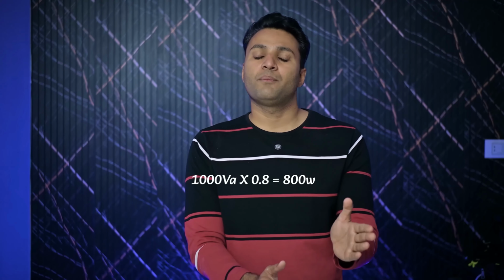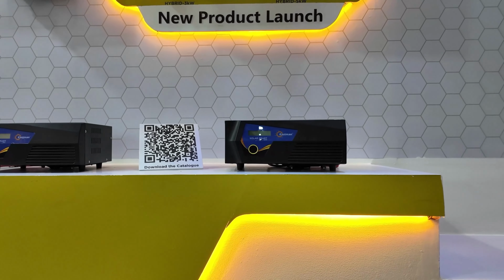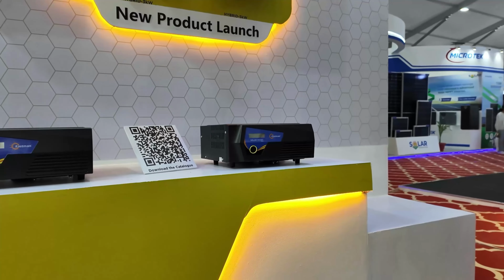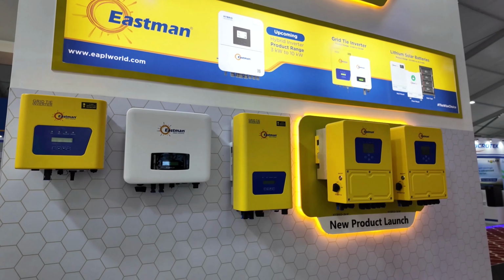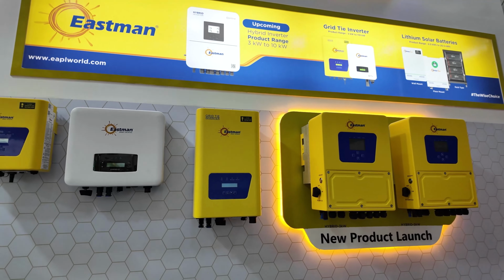For example, when calculating VA, the common formula says that if you have a 1000 VA inverter and its power factor is 0.8, then it can run up to 800 watts load. So if you want to run an 800 watt load, then a 1000 VA inverter should be enough. Or sometimes people even recommend taking 25% extra margin and say you should buy a 1200 VA inverter for that load. But in actual use, it does not work like that. Most inverters available in the market are not efficient enough to be measured properly on 0.8 power factor. Some brands do offer very high efficiency inverters, but their prices are also much higher. Let me explain with examples.